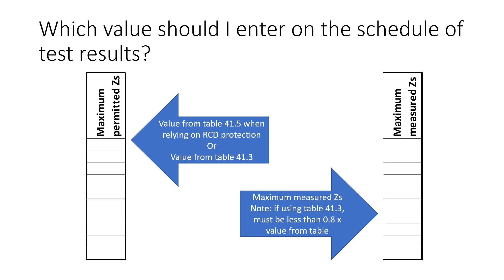So which value should I enter on the schedule of test results? If we are relying on the 30 milliamp RCD for fault protection, then we could use the value required by table 41.5 — so that would be 1667 ohms for a 30 milliamp RCD or RCBO. If the maximum measured ZS is within the maximum permitted ZS required by table 41.3, then I would enter the value from table 41.3 — so that's 1.37 ohms for a 32 amp type B RCBO. But when we record the maximum measured ZS on the right hand side of the test results, we need to ensure that the maximum measured ZS doesn't exceed the formula in appendix 3, which relates to adjusting for operating temperature.